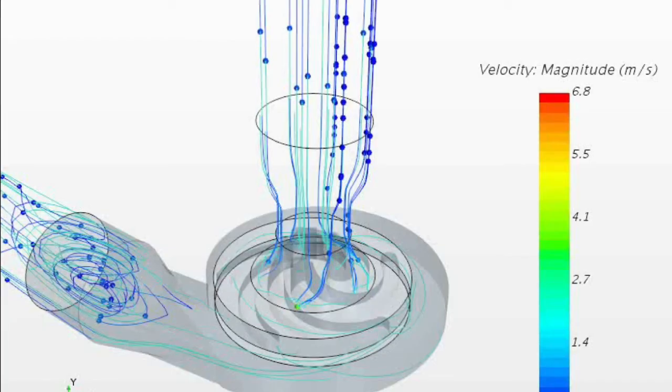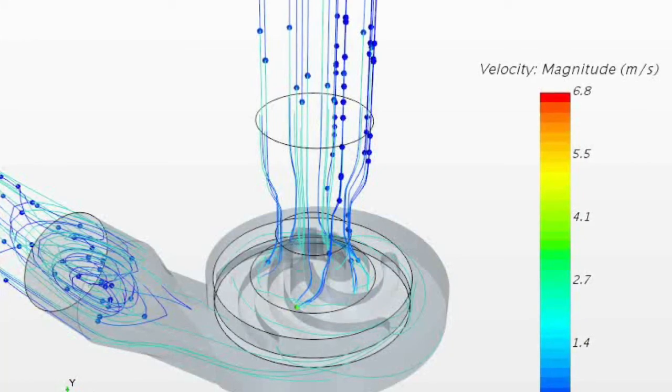In summary, for the algorithm of the Hydraulic Institute, it can be noticed how this method was restricted by the B parameter, because for those fluids with a B greater than 40 and with a Reynolds number that was small, the results were incoherent, for example, presenting power that had a trendline with a negative slope.